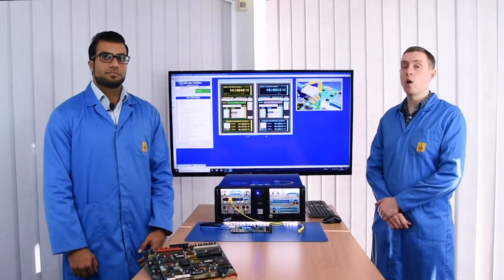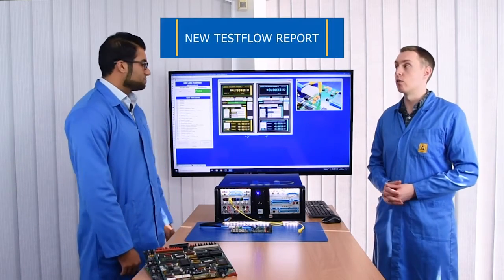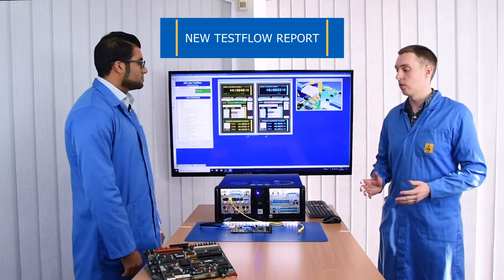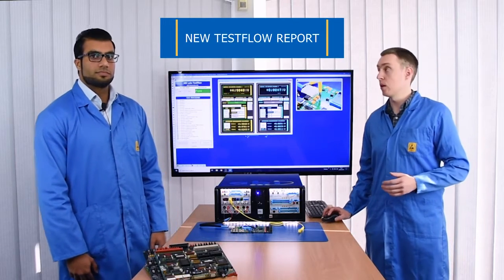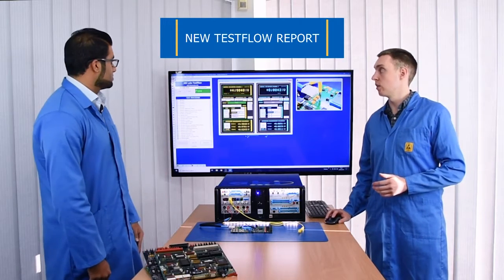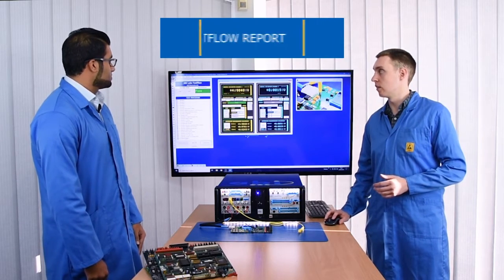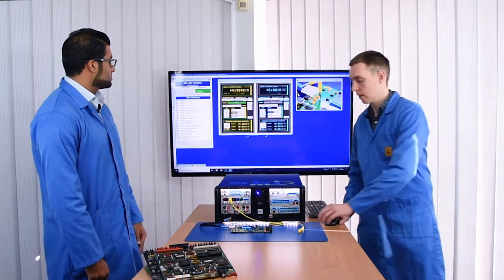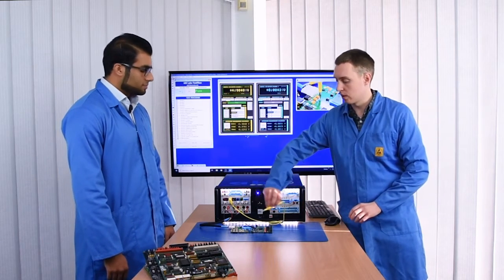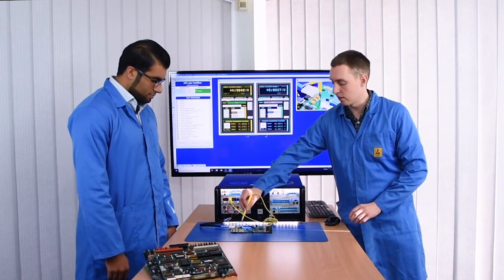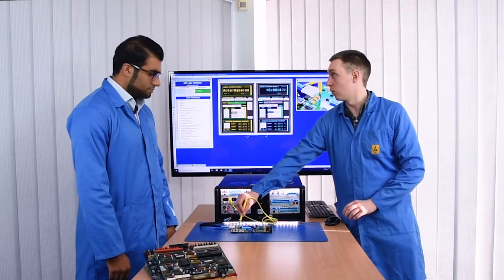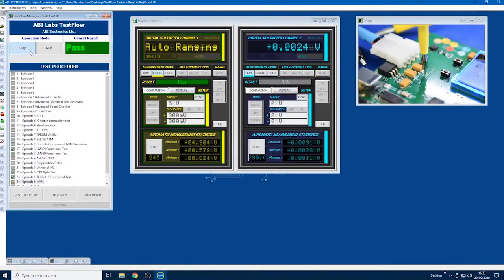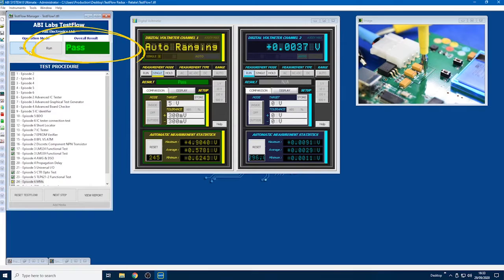Yes, of course. All while I've been doing these tests from start to finish, it's been recording all the data in a report. It's as simple as putting it in step mode as you would as an engineer, and taking a measurement of our point for our final test. We'll get a pass like so. I can take that off and look at the report.